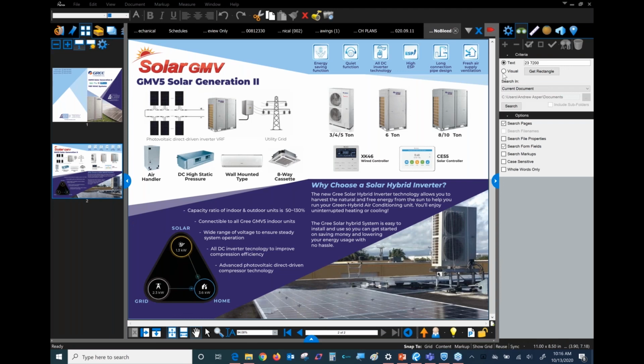Can you twin multiple 8-10 ton units together? I think this is asking about the solar VRF. Yes, that is correct. The 6, 8, and 10 ton modular models can be twinned together up to 30 tons on a system. Heating performance at 24 degrees outside air temperature and producing 130 degree water. I have a request to the factory to pull the derate chart for the hot water unit. I do just have a basic cut sheet that says that it operates down to -4, and I will take note of that and shoot an answer out to you for that.